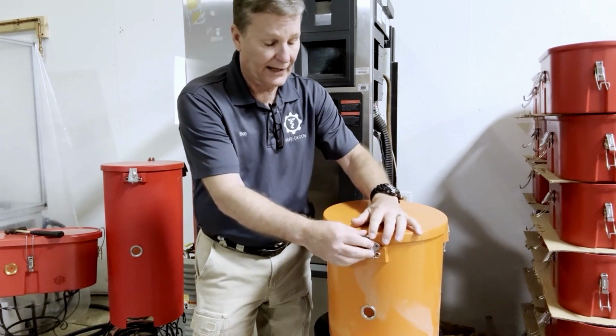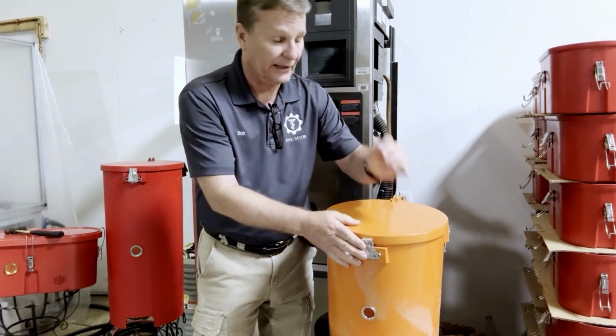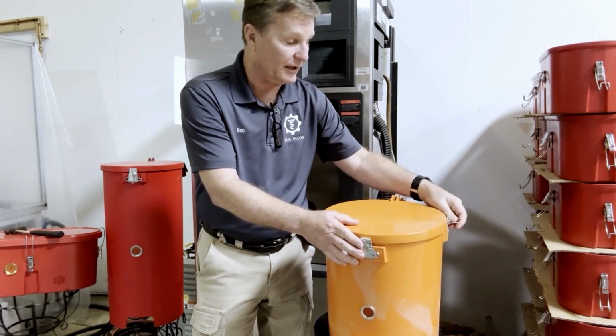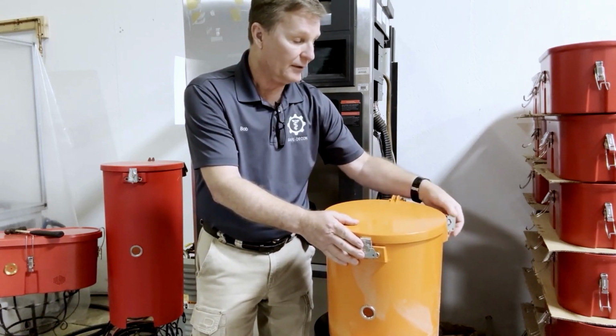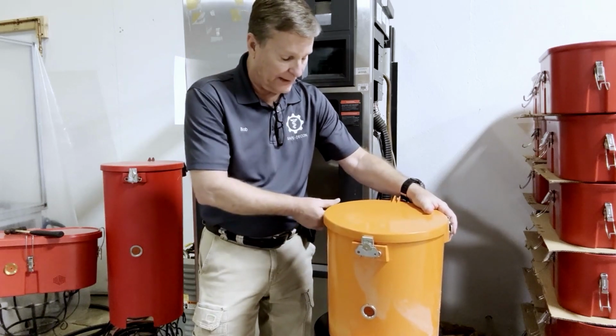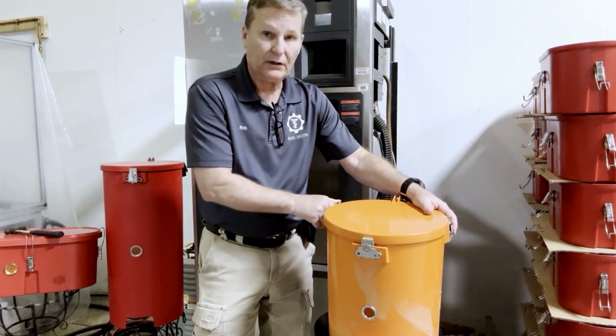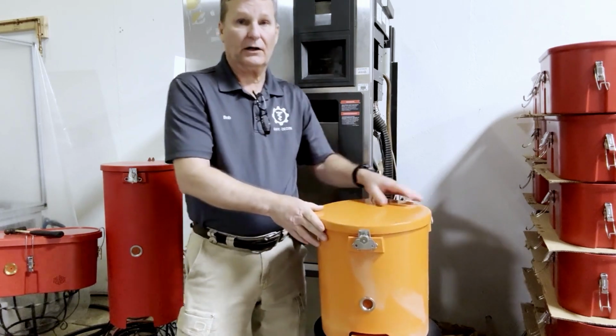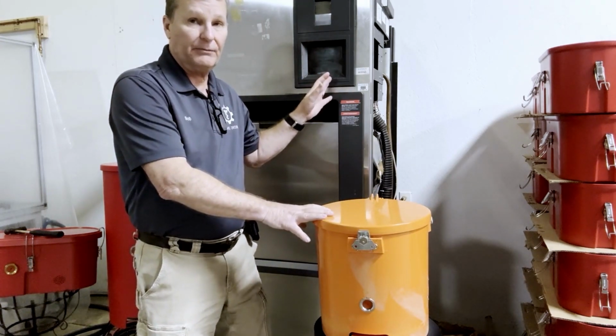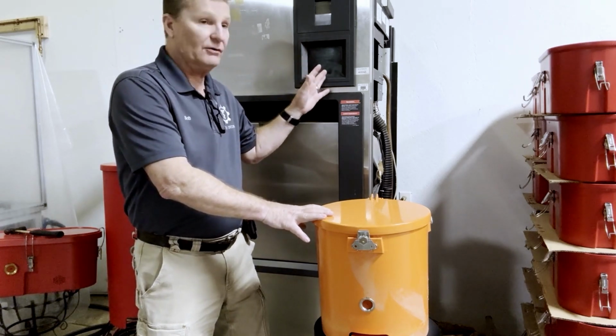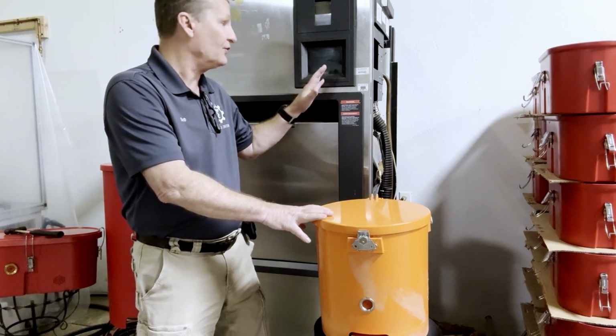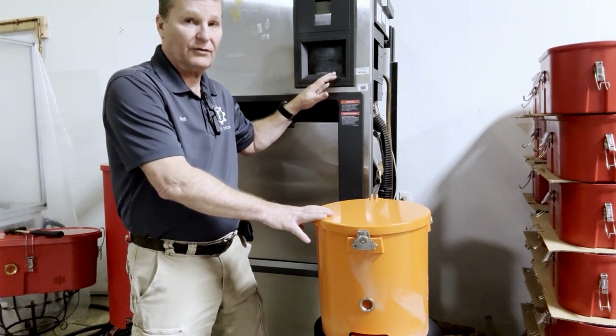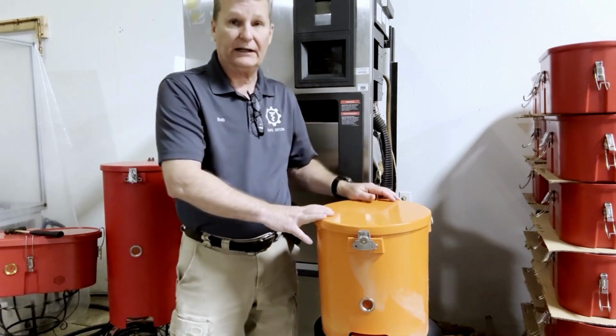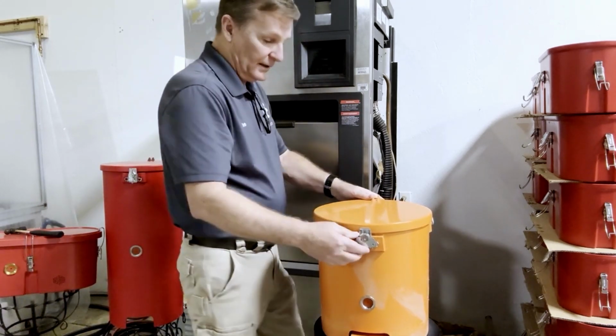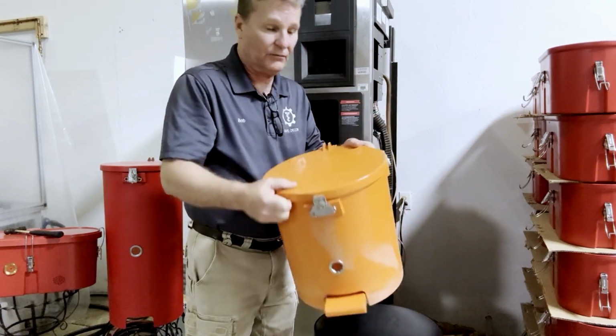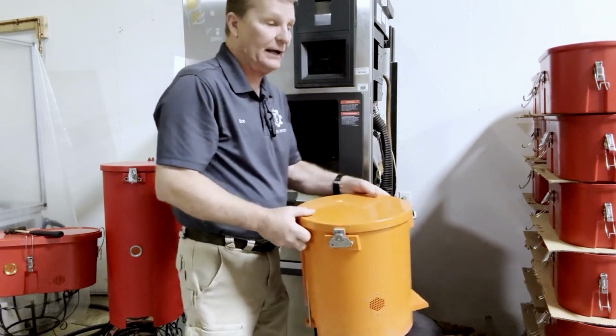Now the cycle I'm running is actually a modified Bowie-Dick cycle. We're running 4 pulses instead of the usual 3. The first pulse is required to open the valves up. Then you'll see the steam penetration on the final 3. The autoclave is set for a 3-minute purge, just like you would have in a regular steam test, dart test. It is a 4-minute sterilization at 132 Celsius or 270. So now that we got this thing locked up airtight with our Bowie-Dick inside, let's run it and see what happens, folks.